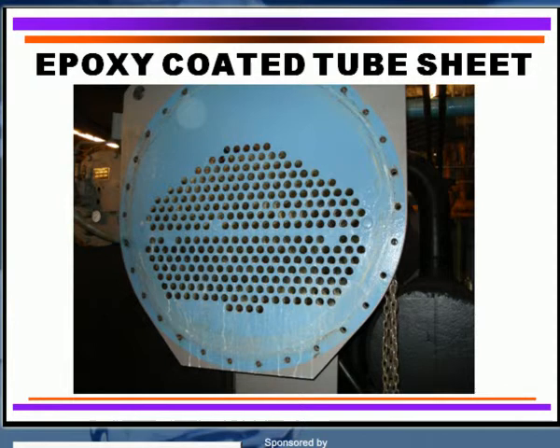Here's a good example of an excellent project of having an epoxy coated tube sheet. That's going to give you a long life and reduce your water treatment chemical requirements. It'll improve the protection of your equipment and make it last a lot longer.